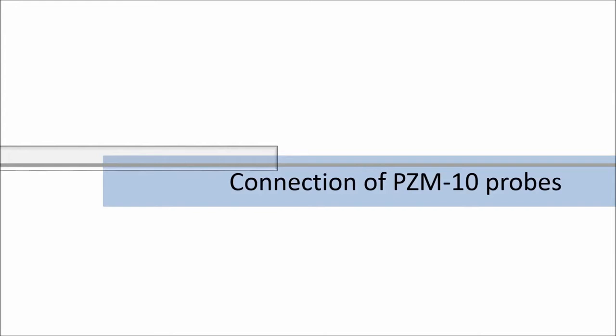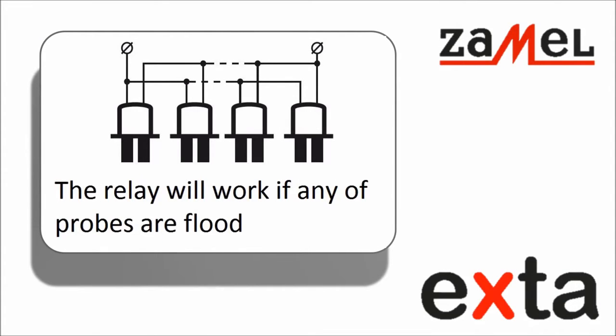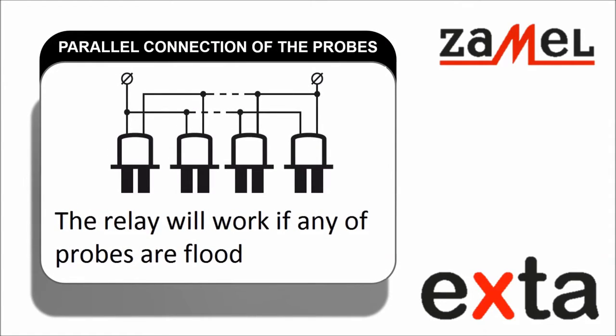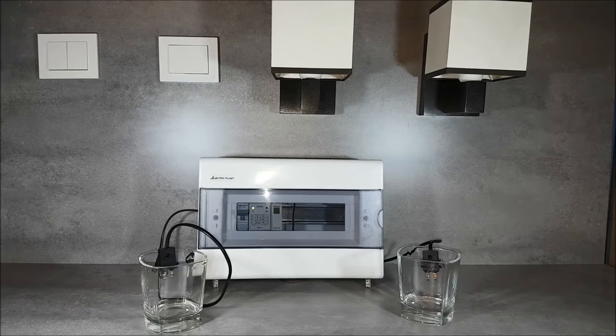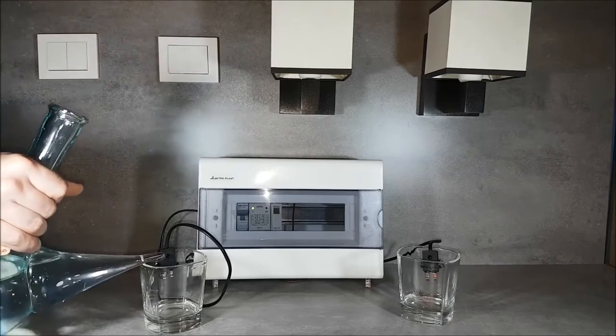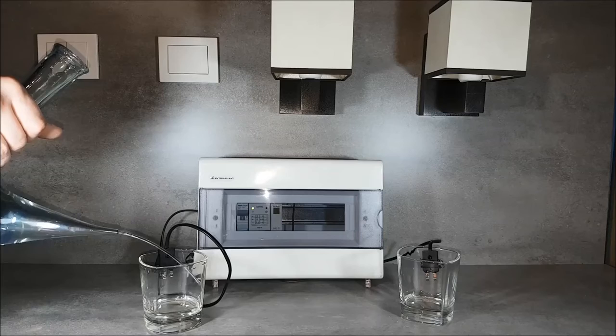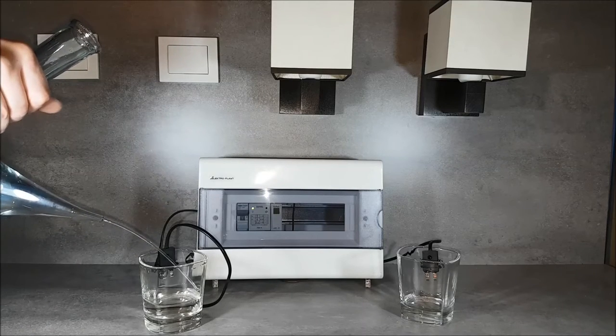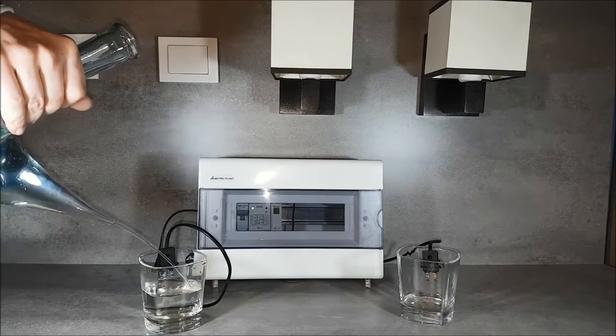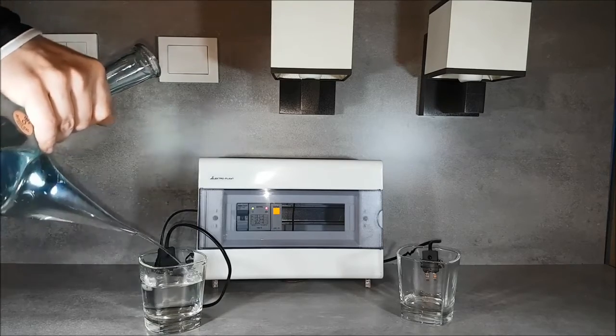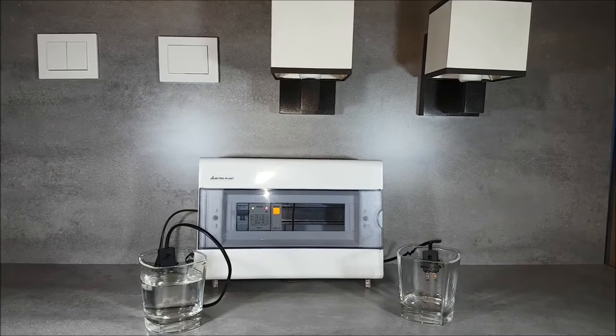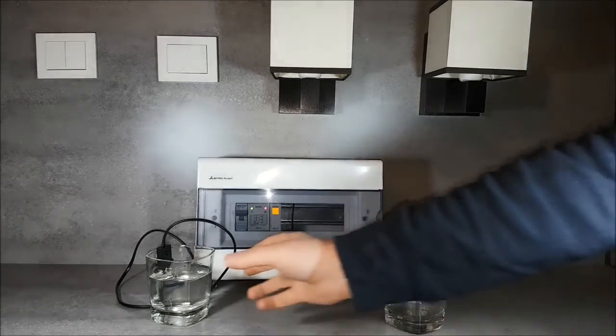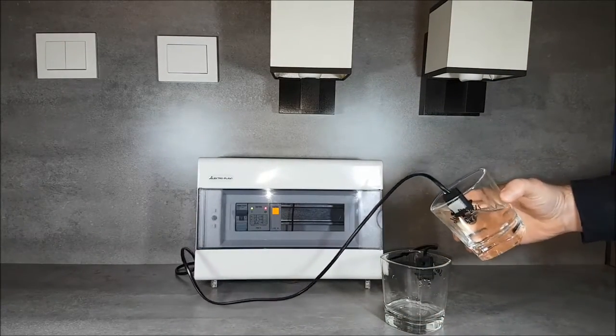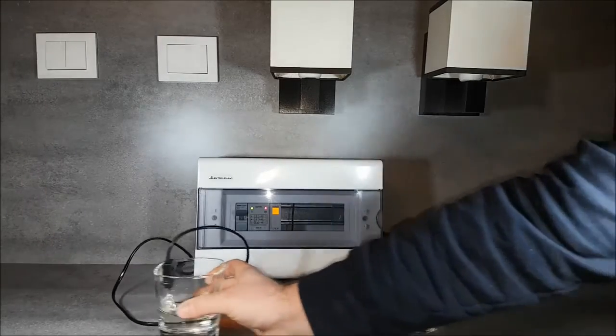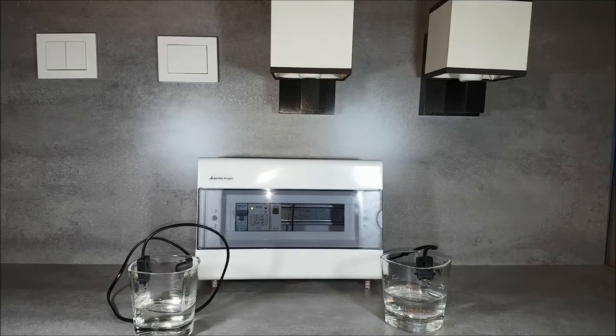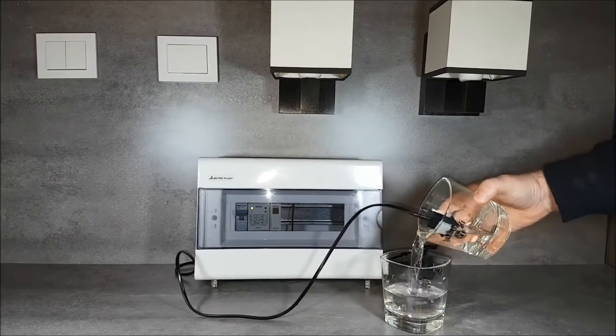Once SZH01 probes are connected in parallel, flooding any of the probes causes the PZM-10 relay to operate. Flooding first probe. Flood detection is signalized by the LED. After decreasing the liquid level, none of the probes is flooded. After flooding of the second probe, the PZM-10 relay outputs are triggered.